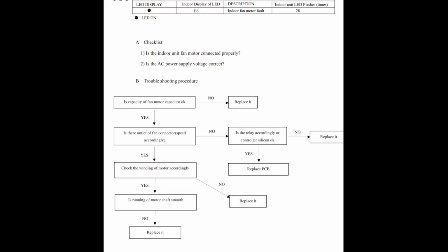Is the outlet of the fan connector speed accordingly? Of course, everything's hooked up the way it should be hooked up. Nothing has changed. Check the winding of the motor accordingly. Measure ohms, measure to ground. If you don't have any off readings, then is the motor shaft smooth? You're going to have to take the motor out. You're going to have to spin the fan motor shaft and make sure there are no rough spots. Of course, this one, it comes on.